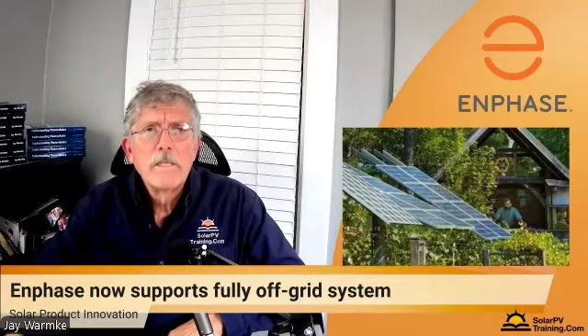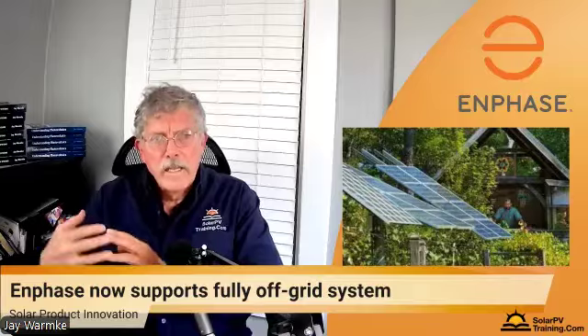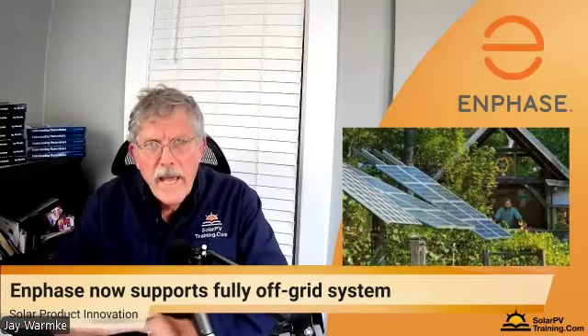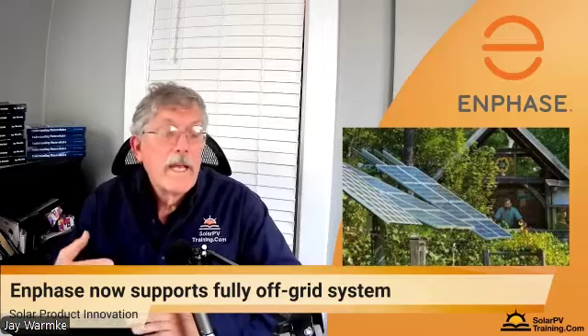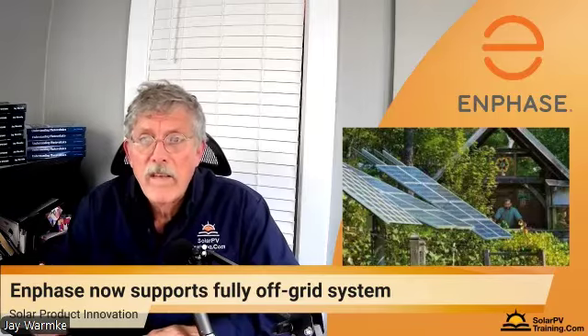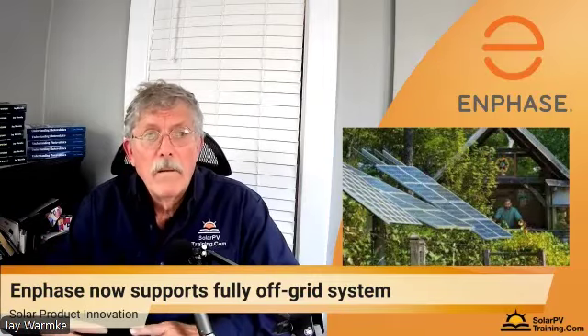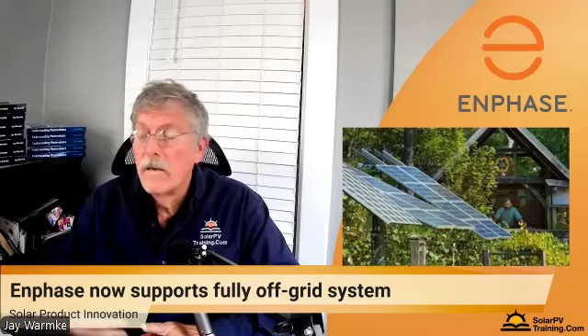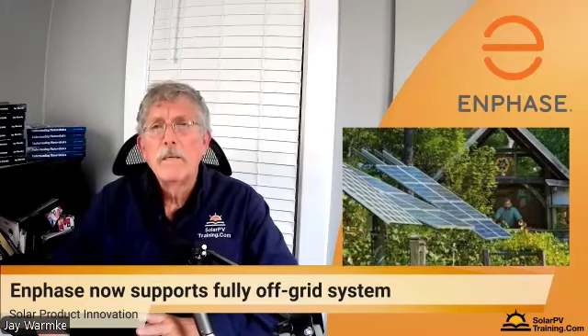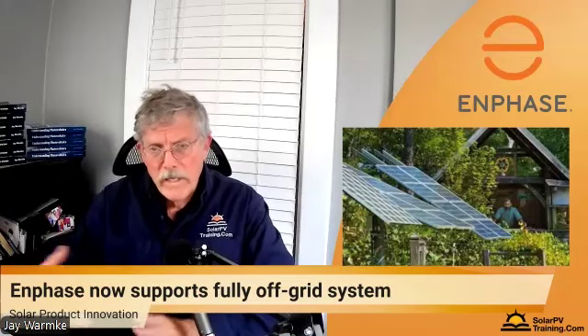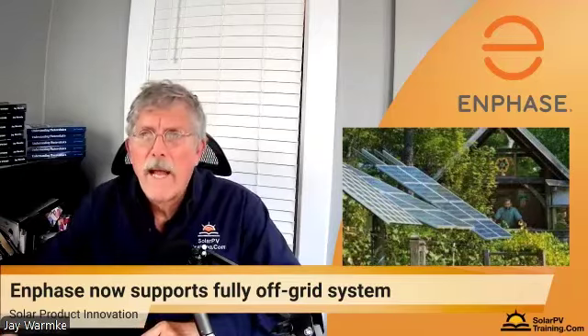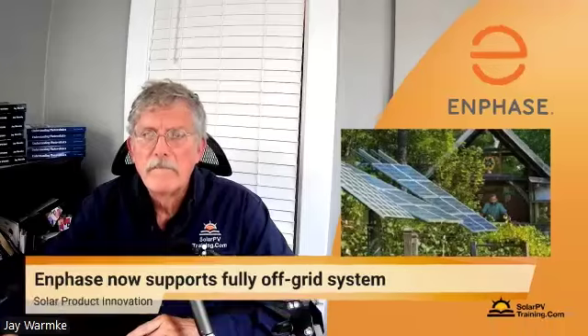The IQ System Controller 3G connects together with the array, the batteries, and the generators, and it can handle up to 46 kVA of off-grid power. For isolated sites, the IQ Combiner also includes a cell modem so that it can transfer all the data without any kind of local broadband connection.